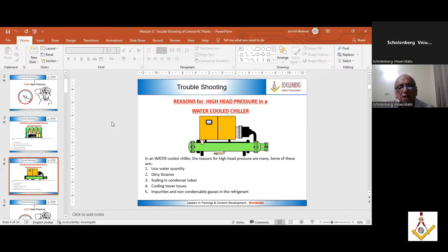That question was for high head pressure. As long as you've opened the module, you can go through all this. For high head pressure of a water-cooled system: less water flow, dirty strainer, scaling in condenser tubes, cooling tower issues, impurities of non-condensing gases in the refrigerant.